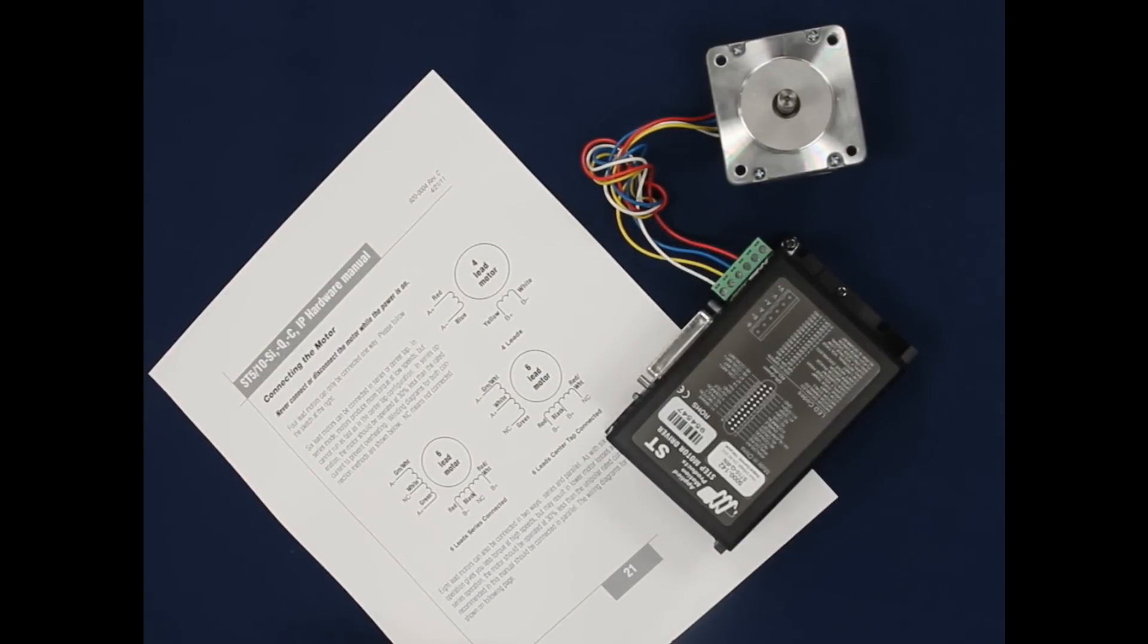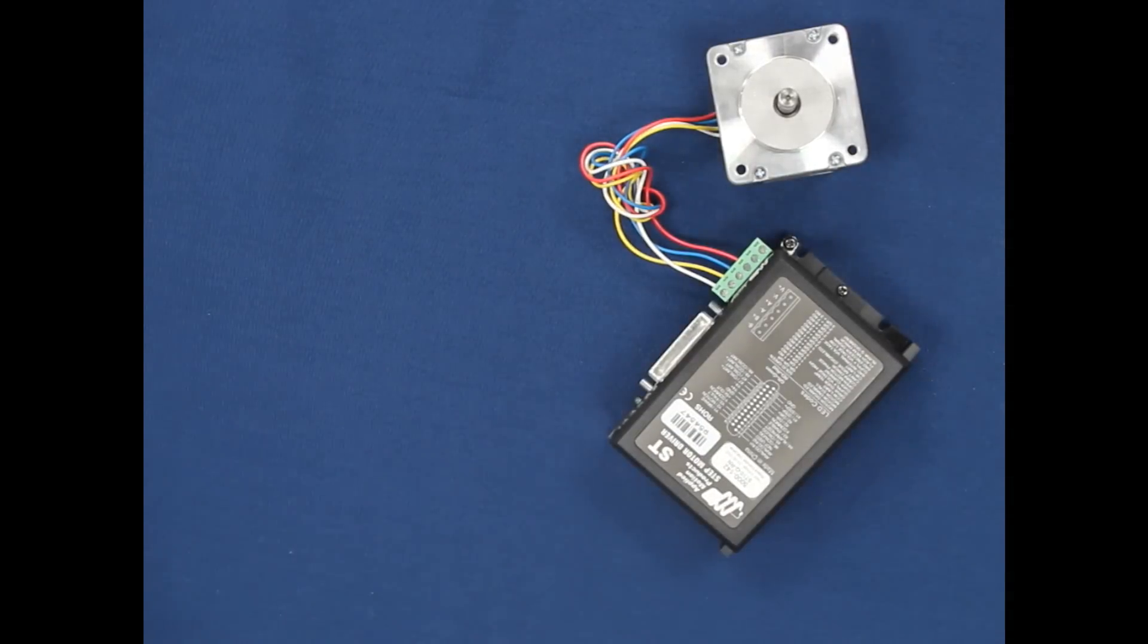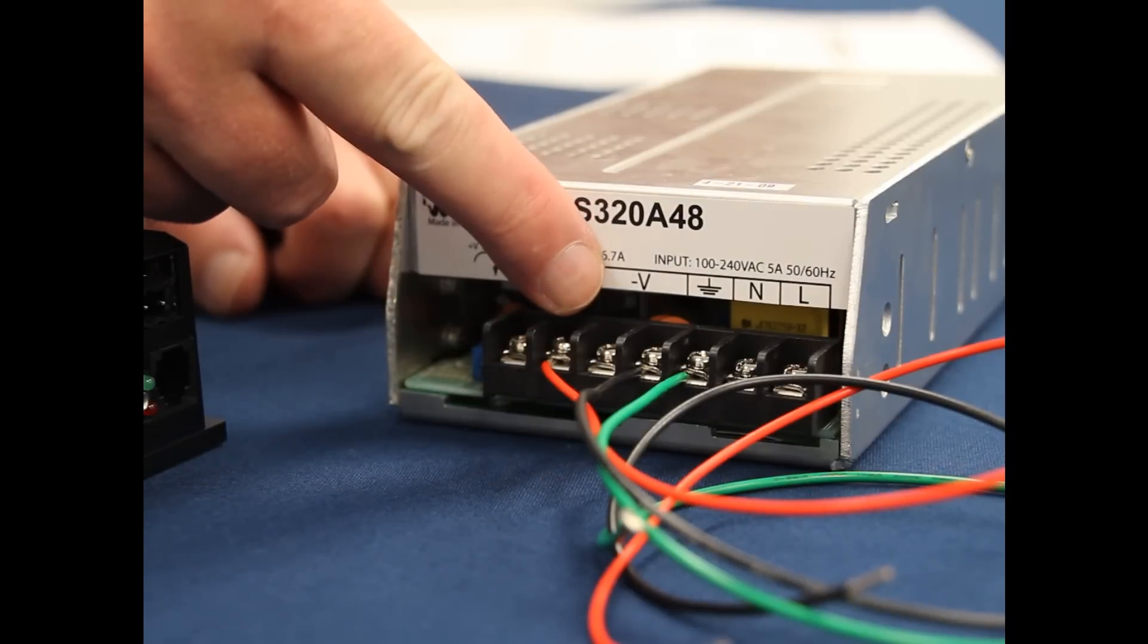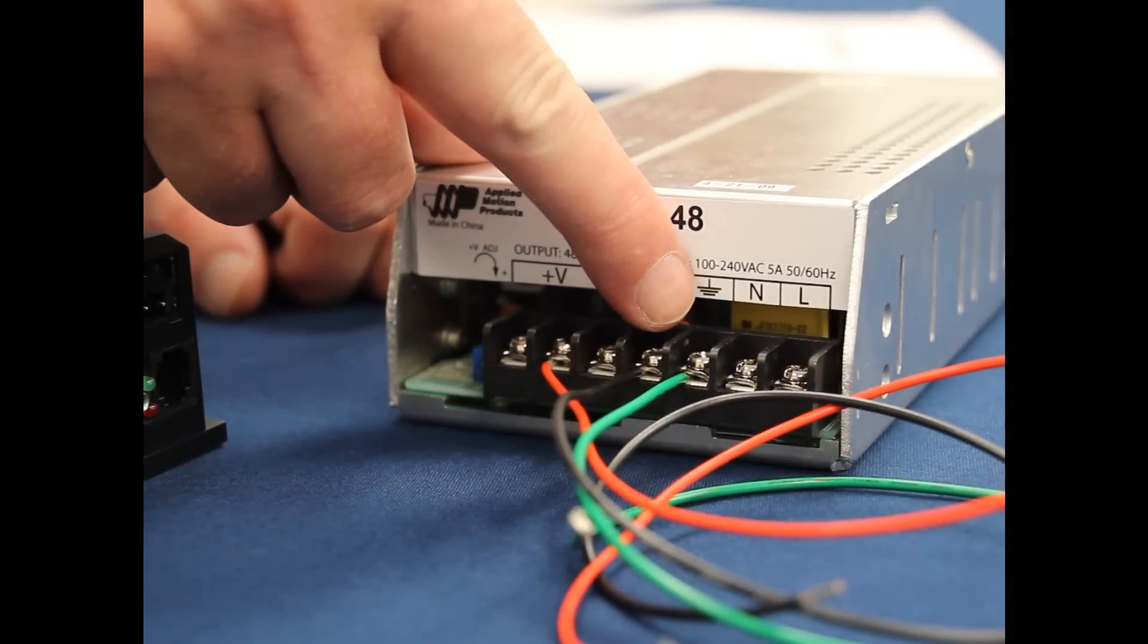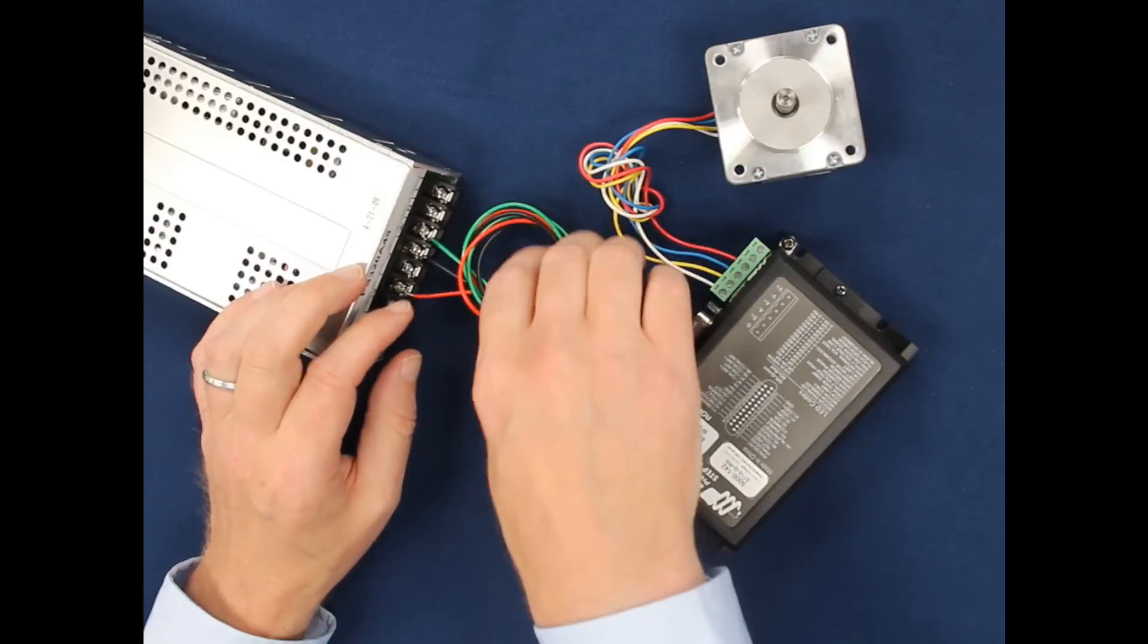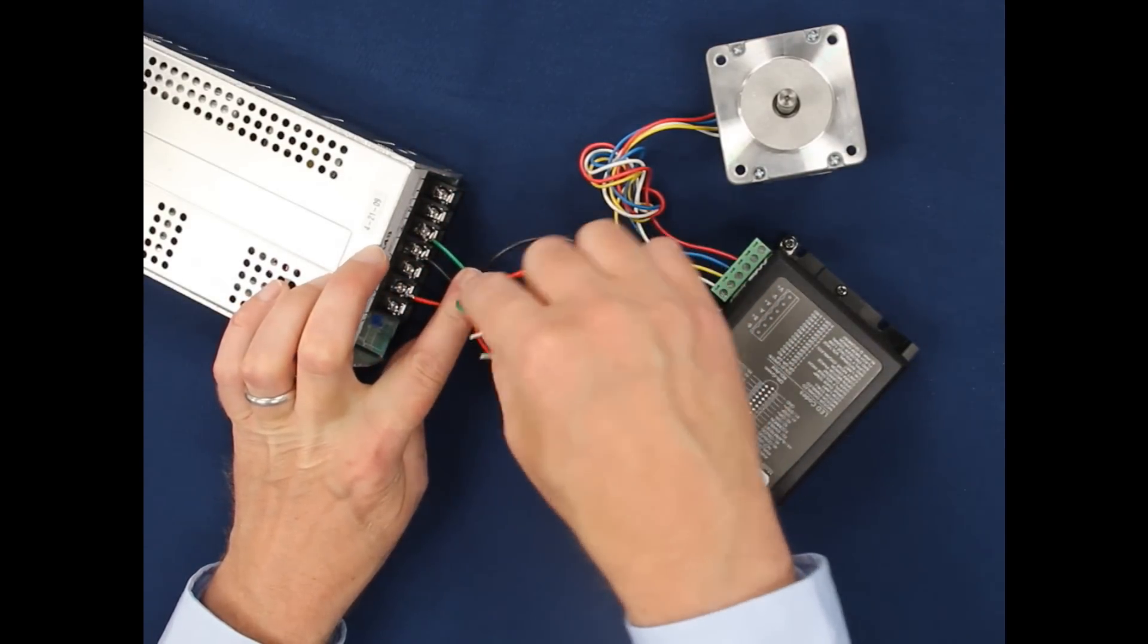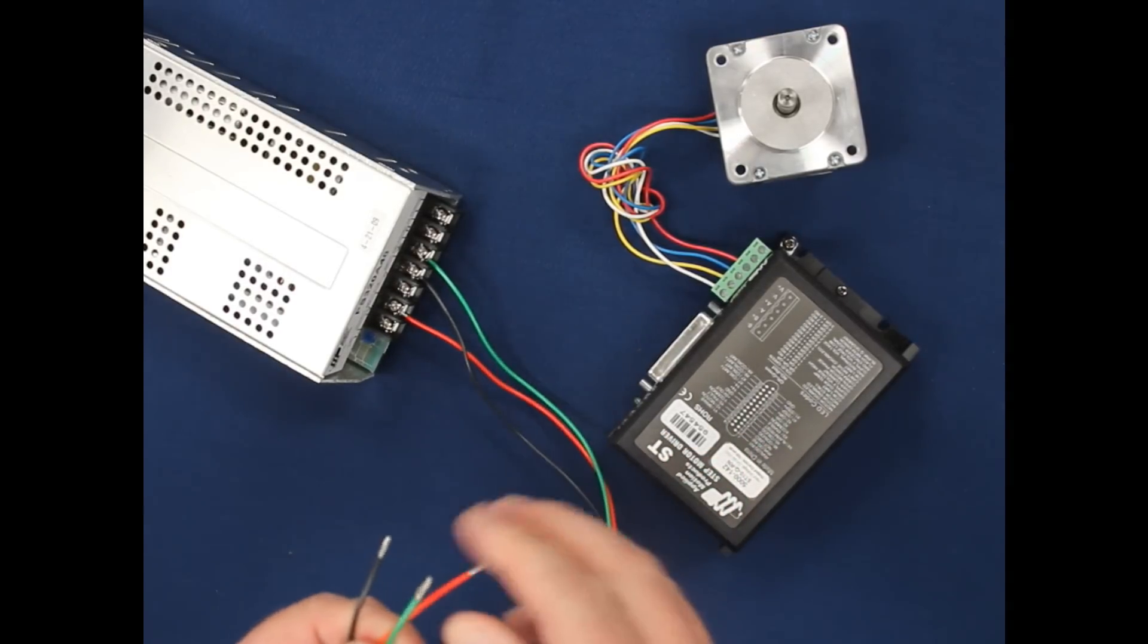Now we need to connect the power supply. This time, just two wires. I'll move the motor instructions out of the way. I've already connected the power supply end. My red wire, by convention, goes to the positive DC voltage. The black wire goes to the negative DC voltage, and this green wire is going to be my chassis ground. That will make sure that any electrical noise goes where we need it to go, namely to earth ground, rather than somewhere we don't want it to go.